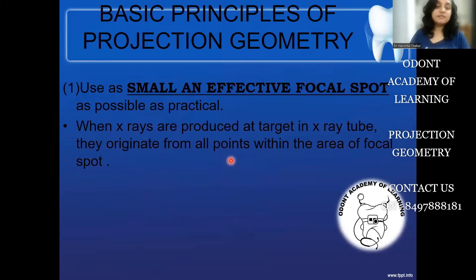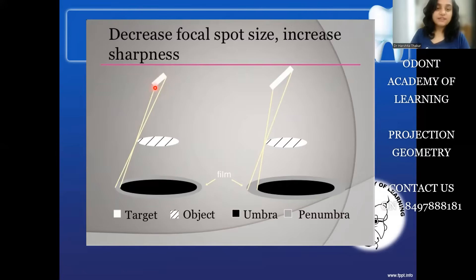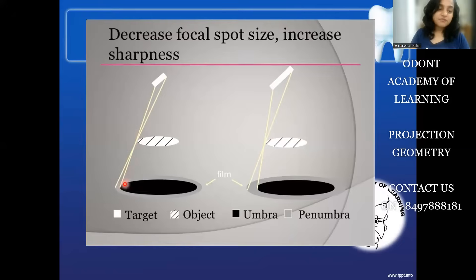The first principle says that we must use as small and effective a focal spot size as possible. Here are two images — image A and image B. The difference between them is the size of the focal spot. In image A, the focal spot size is slightly smaller; the x-ray photons originate from the edges, hit the tooth, converge, and then diverge to form the image. Towards the periphery where these x-ray photons are diverging, they form something called penumbra.